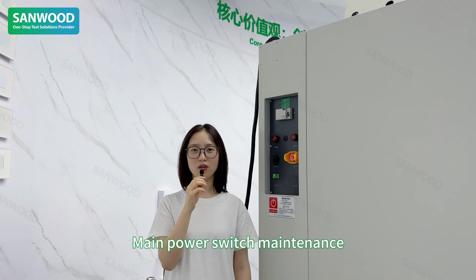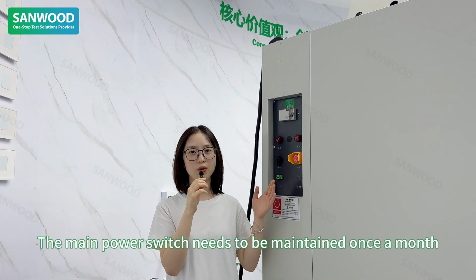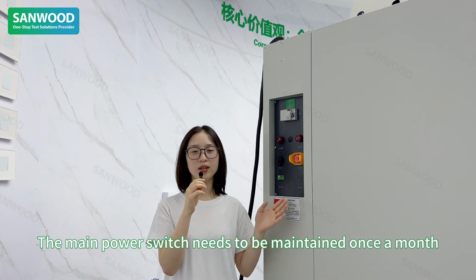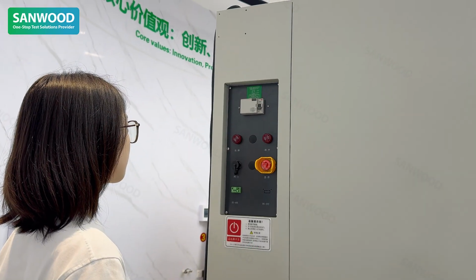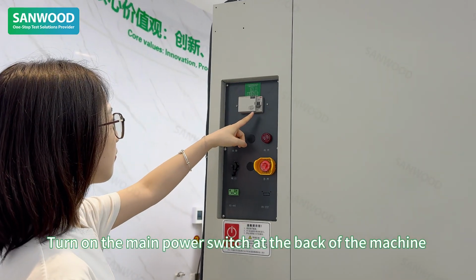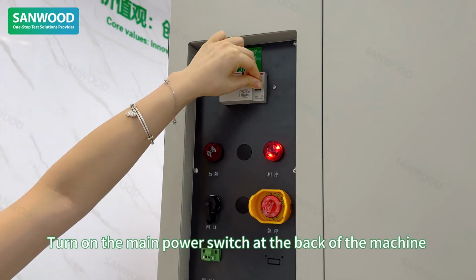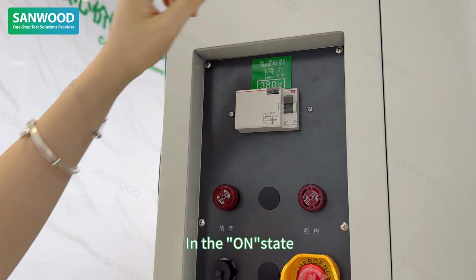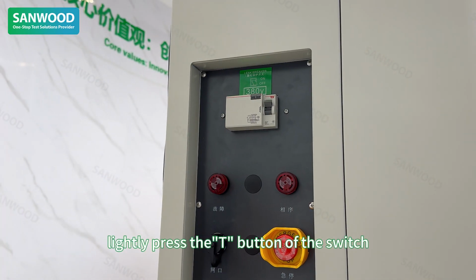Second, main power switch maintenance. The main power switch needs to be maintained once a month. Step 1. Turn on the main power switch at the back of the machine. Step 2. In the on state, lightly press the T button of the switch.